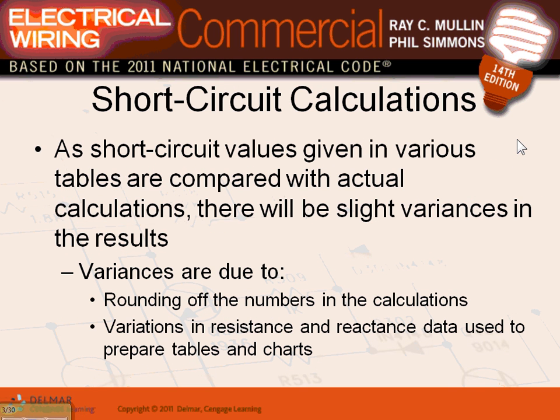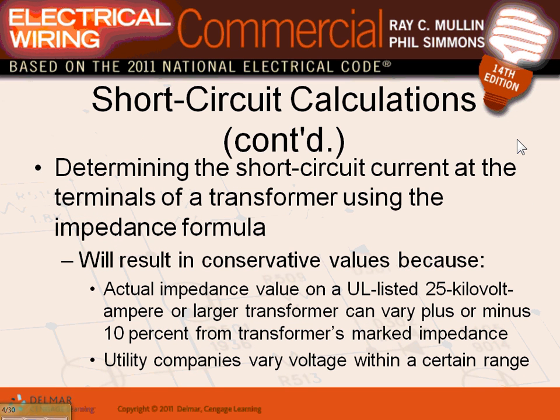So these are a few things, guys, that we need to know. This is just a disclaimer. When you do the tables, the answers might not be the same because of approximation. We don't use the tables. We usually use software, and from the software later on, you're going to see. Remember the estimating software you guys are using? The power system analysis software has a library that comes with it. If you need a transformer, all the transformers that God created are in the library. Conductors, all the THHN, THHW, XHHW, all these medium voltage cables, are in the library of these systems, so you can pull all this information, the impedance and so forth.